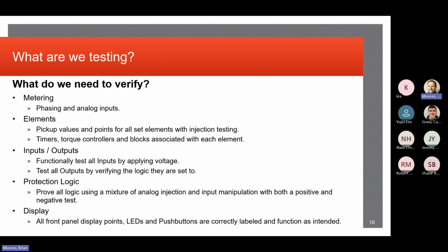Great questions. What are we testing? All right, so we've got a relay. It's connected to voltages. It's connected to currents. It's connected to outputs. It's got some inputs. There's all the stuff outside the box, and there's all the stuff inside the box. So we want to test everything that we can to validate that the relay sees what it needs to. So at the end of the day, what we're hired to do, when we're testing this stuff, we want to make sure if that relay sees an abnormal system condition, it's going to operate the way that the design engineer and relay settings engineer intended it to operate.